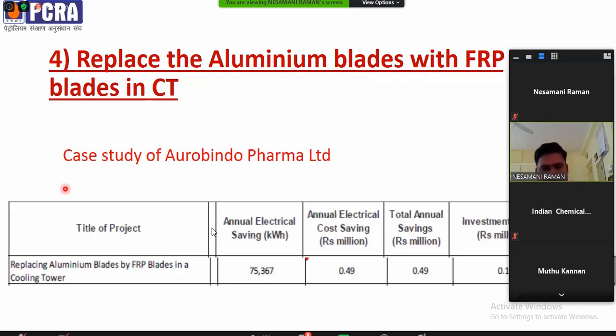So I have a case study of Aurobindo Pharma. They replaced the aluminum blades with FRP blades in cooling towers, and they achieved savings of almost 75,000 units of electricity, which is equal to almost 0.49 million rupees of savings. Payback was very short, only 4.3 months.